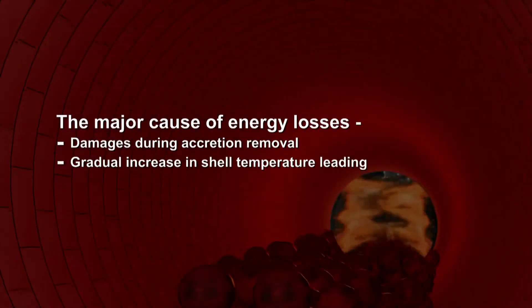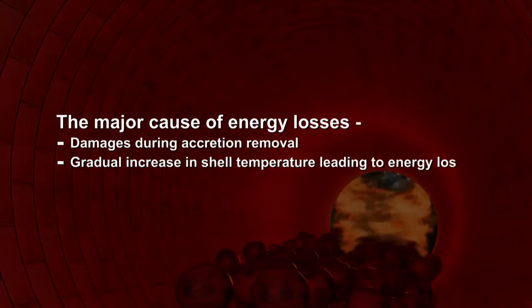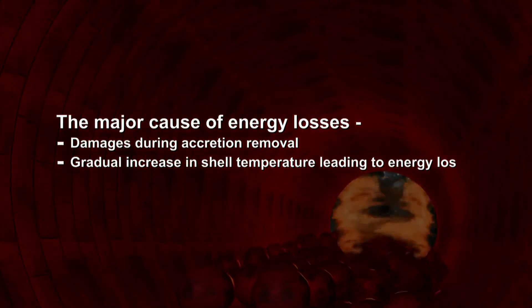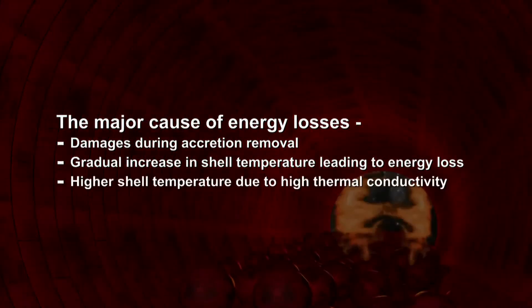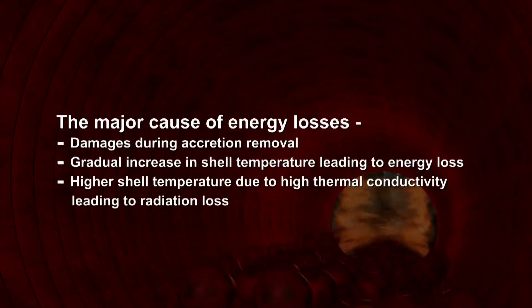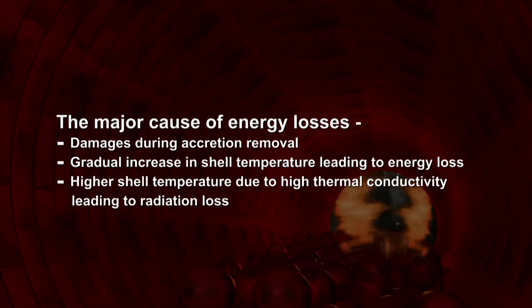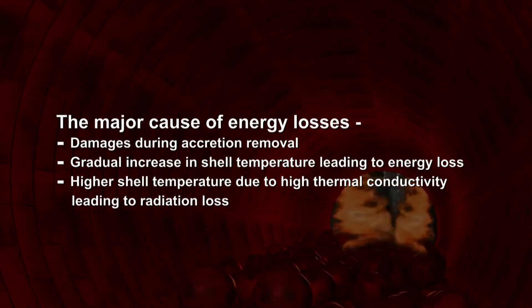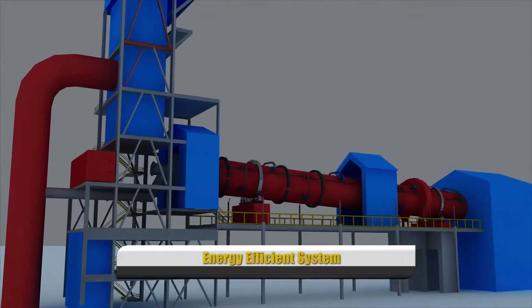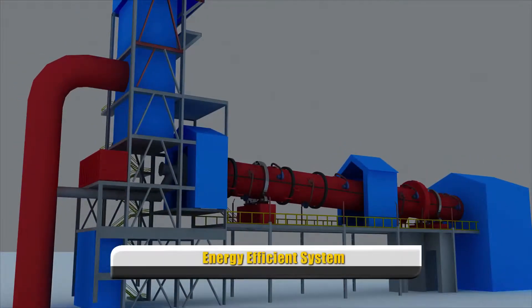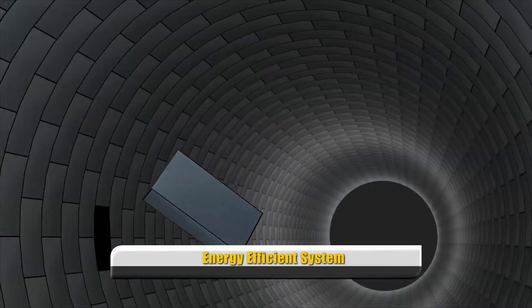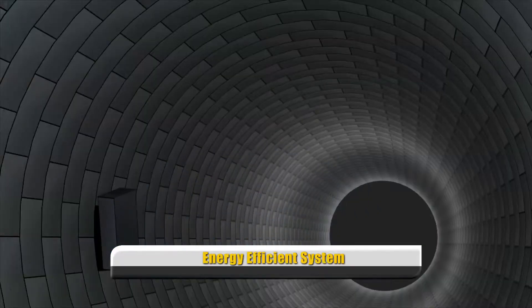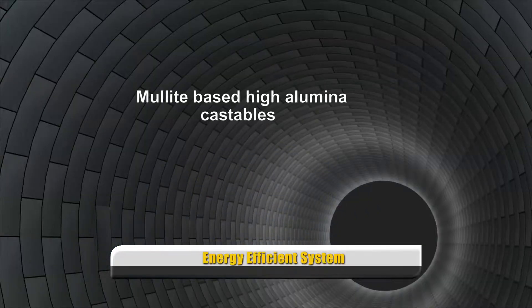gradual increase in shell temperature leading to energy loss, and higher shell temperature due to high thermal conductivity leading to radiation loss. The energy efficient replacement for high alumina low cement castables are mullite based high alumina castables.